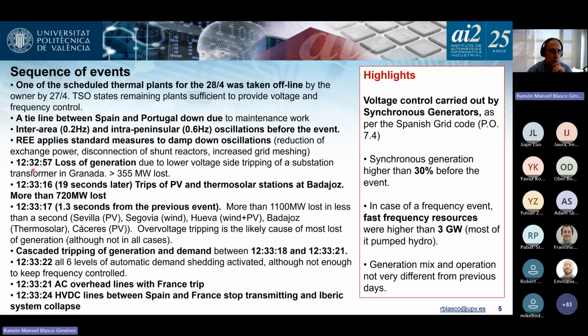At 12:32:57, there's a trip in a substation in Granada on the low voltage side of the transformer, and there were more than 355 megawatts lost. 19 seconds later, there were trips on PV and thermal solar stations in Badajoz, which is also southern Spain, very, very close to Portugal, more than 720 megawatts lost. We're talking 19 seconds here.